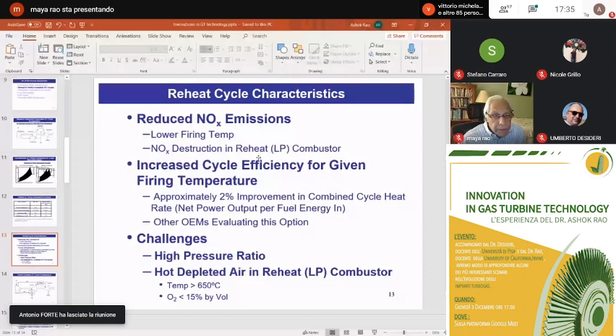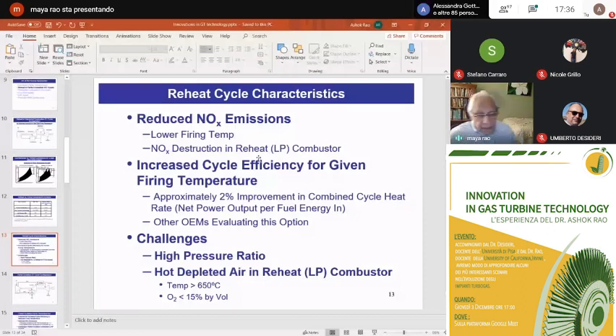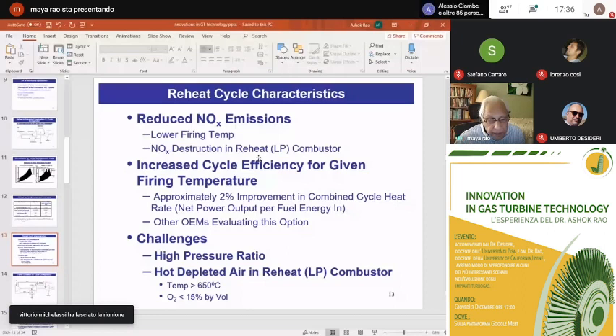And as I mentioned, you need much higher pressure ratios, which also means much higher temperatures for both the reheat combustor as well as the LP combustor. You're talking about in excess of 650 degrees Celsius. And for the LP combustor, the reheat combustor, you're dealing with an oxidant that has a much lower oxygen content. It could be less than 15% instead of being 21% with air.